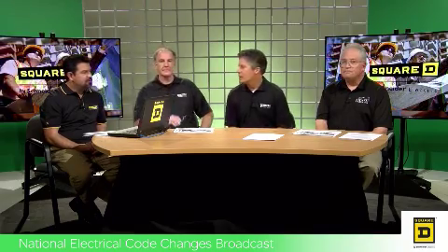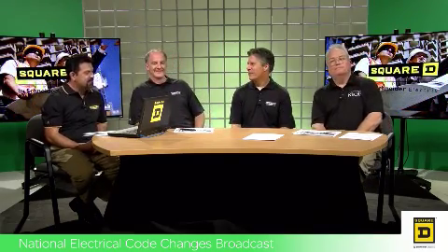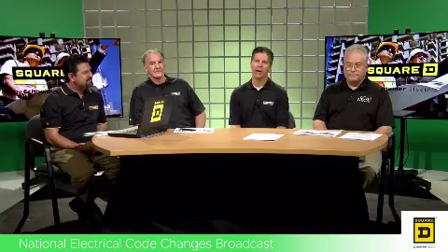Good, good. So Chad, I'm going to pick on you next. Power monitoring equipment in Section 312.8. Right, so power monitoring equipment. A lot of customers are asking for a way to measure power within the electrical equipment. And we've had really undefined requirements in the National Electrical Code on how you do that, where it can be located. And we've had instances where authorities having jurisdiction or the electrical inspector is not comfortable with this equipment, such as current transformers and other devices associated with the power monitoring or metering being located in the wiring space. So this change is really a great benefit to that.